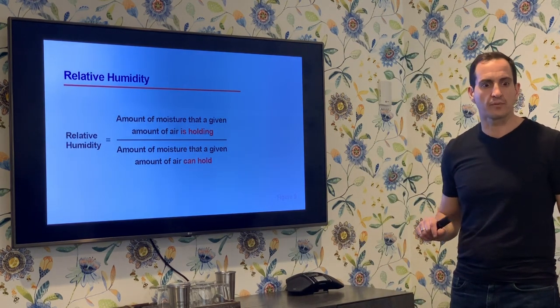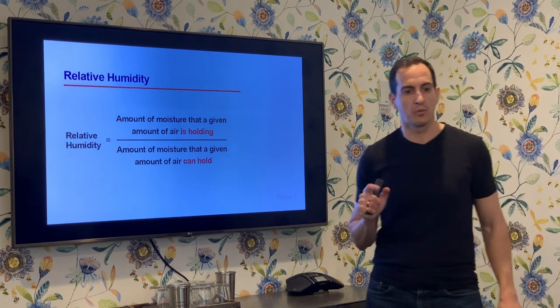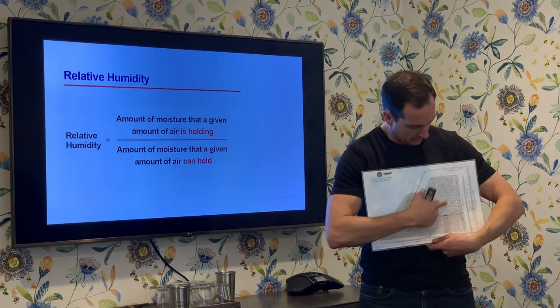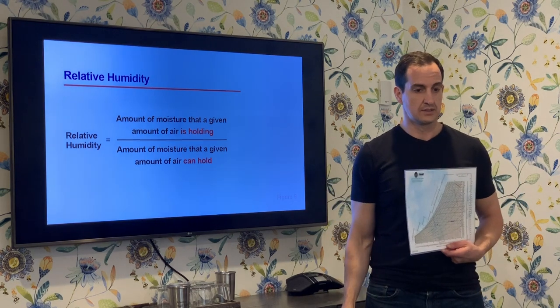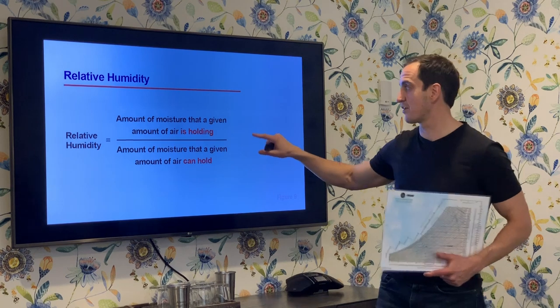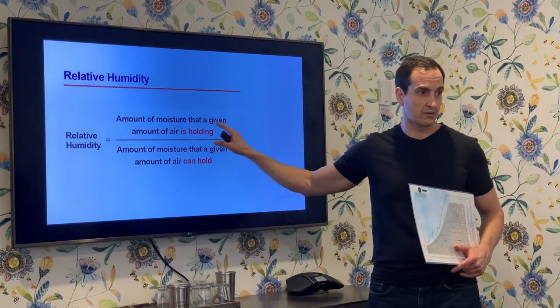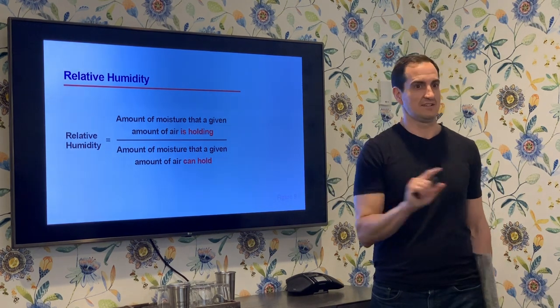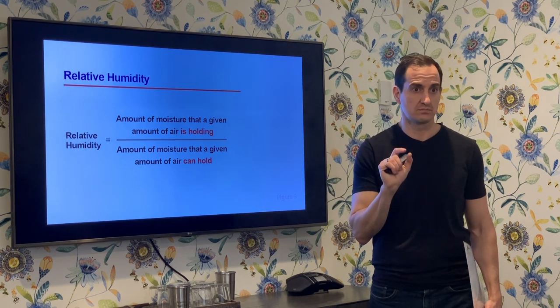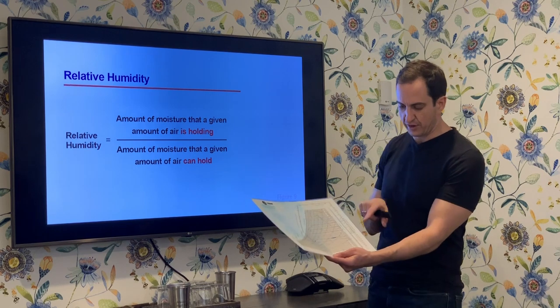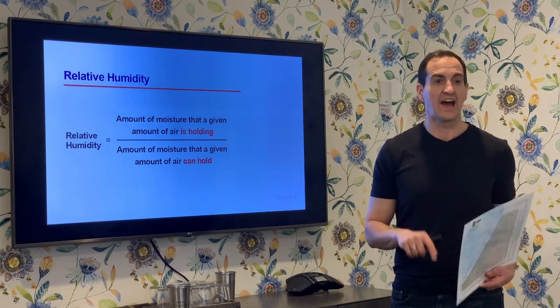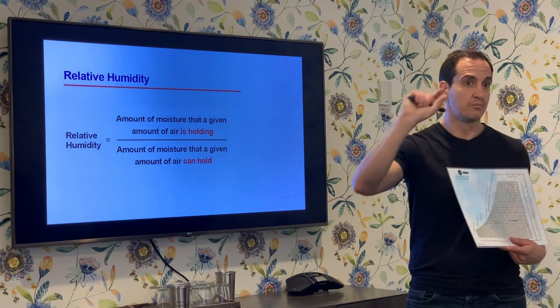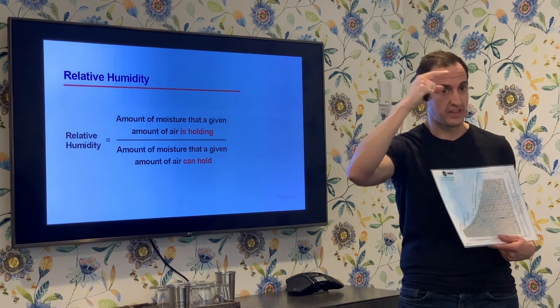Let's talk about relative humidity. We see these swooping lines — the bottom one is 0% and they swoop up to 100%. It's very important to note that relative humidity is the amount of moisture in a given amount of air over the amount of moisture that given amount of air can hold. It is not a measure of how much of the air is water. If you look at the humidity ratio, you'll find that at 100% relative humidity we're not talking more than one or two percent of actual water molecules.